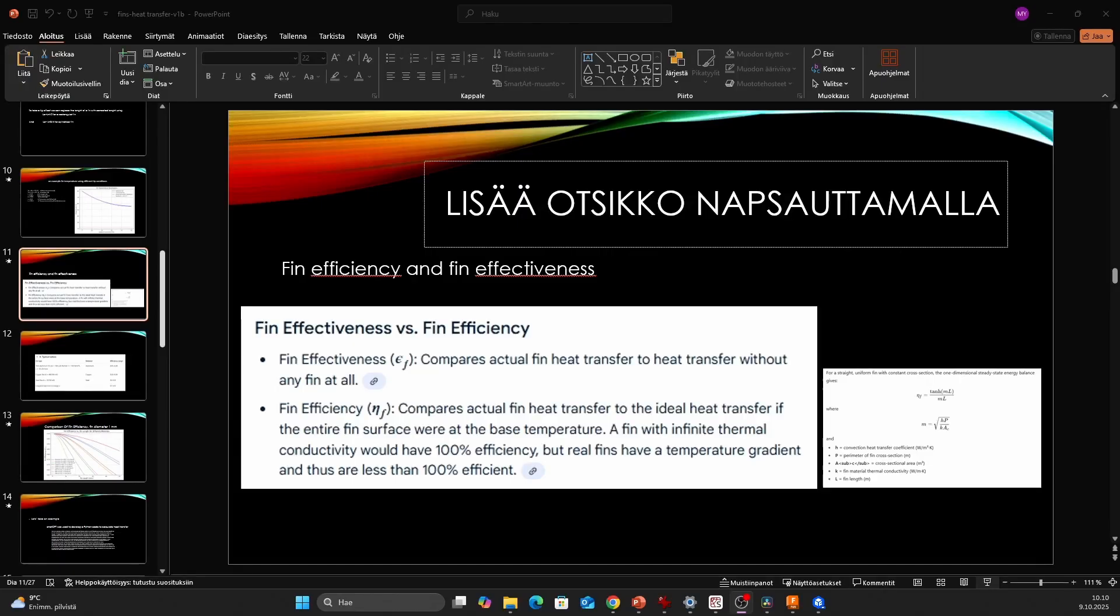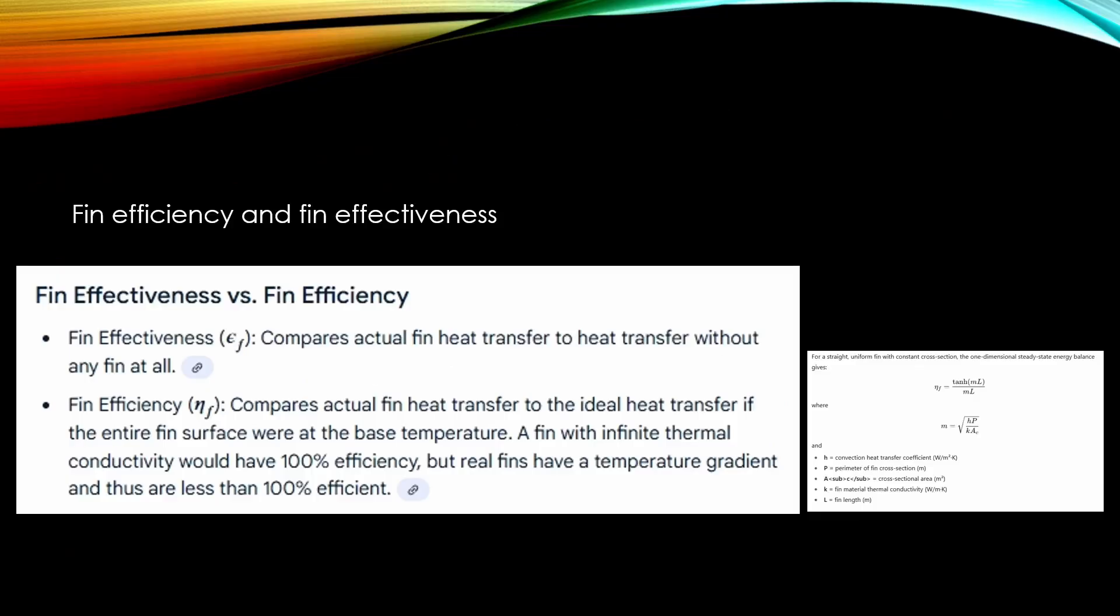When we are working with fin design we quite often meet some terms which can be very confusing. These are fin efficiency and fin effectiveness. With fin effectiveness we compare the situations with fins and without fins. For example, heat transfer from a pipe without fins compared to situations when we have fins.